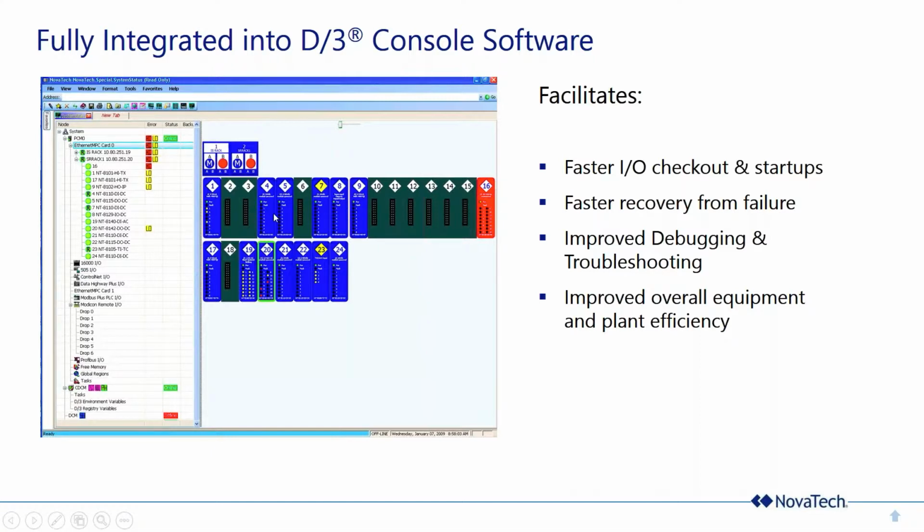It automatically, when you select the eBIM, which is the second one here, the one that's blue, I believe, is the selected one, it automatically looks at that eBIM and finds out how many carriers are connected to it. So it knows there are 3 carriers. It then looks and finds out what modules are connected to those carriers. And it shows the modules. And those are graphical representations of what you would see out in the field of the module. That red module has failed. And it shows it very visibly in this graphic.